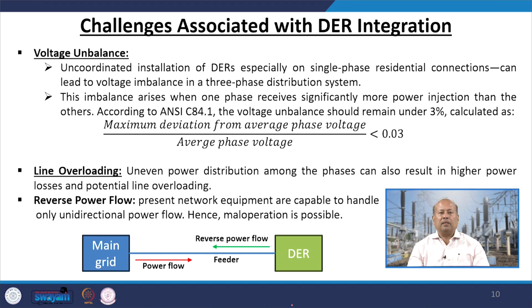According to ANSI C84.1, the voltage unbalance should remain under 3%, and which is calculated in the following way, the following formula, that is maximum deviation from average phase voltage upon the average phase voltage must be less than 0.03, that is must be less than 3%. All right. So, maximum deviation from average phase voltage upon the average phase voltage must be less than 3%. So, we need to assure that it is not going to increase. Now, in case of line overloading, uneven power distribution among the phases can also result in higher power losses, and potentially it may create line overloading.